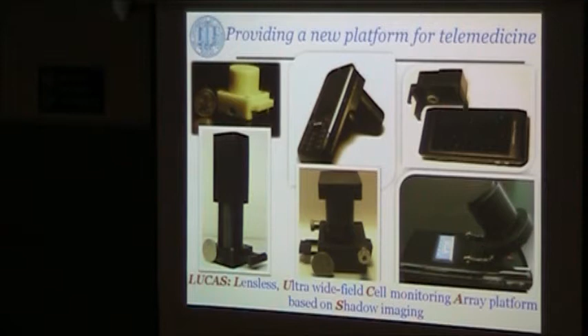So it doesn't require any of these advanced objective lenses or the other bulky optical components that you would normally find in a microscope. As a result, as you can see in the background picture, these are fairly compact and, at the same time, cost-effective microscopes. One unique feature of this platform is its imaging volume. Its imaging field of view and volume is significantly larger compared to conventional designs, which is quite important because most often a disease state is like finding a needle in a haystack. That's why you need high throughput microscopes, and these are actually unique in that sense.